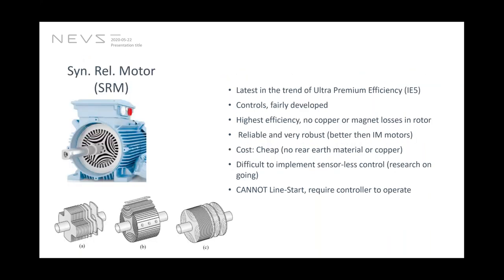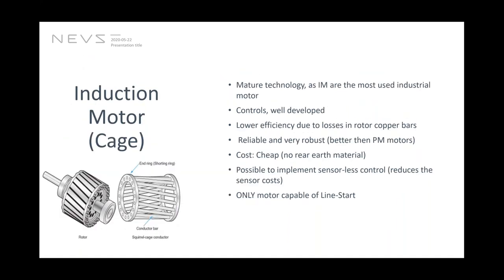I don't know about the synchronous because it's a very limited product. You don't have very many manufacturers who are producing this, and usually these are quite scalable, so you can order. I don't know the range of it, but induction motor, yes, you can get from a fraction of a horsepower, a fraction of a kilowatt, to more than hundreds of kilowatts. So yeah, the induction motor range is quite wide. You can find it on any of the manufacturer webpages, what might be the range of it.